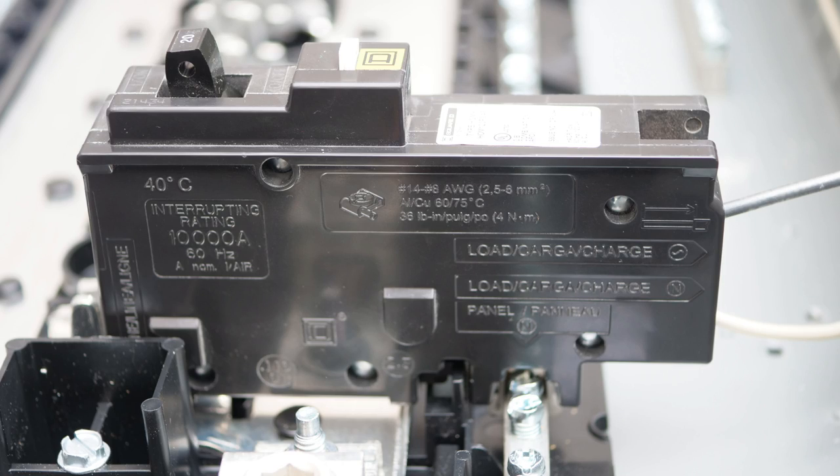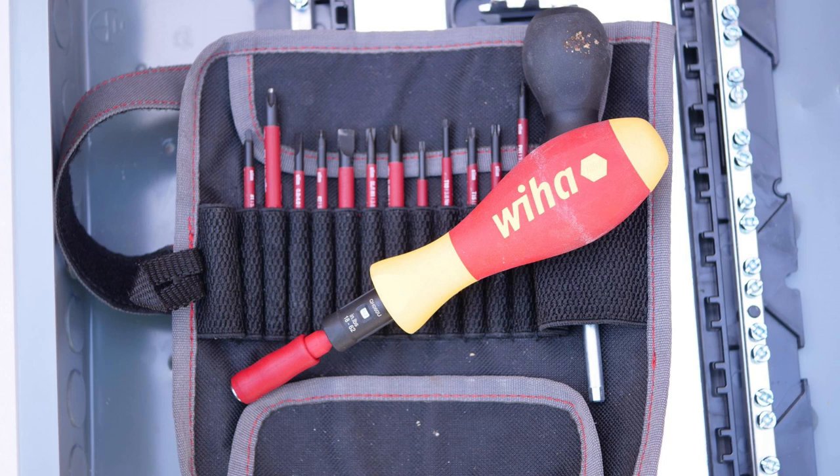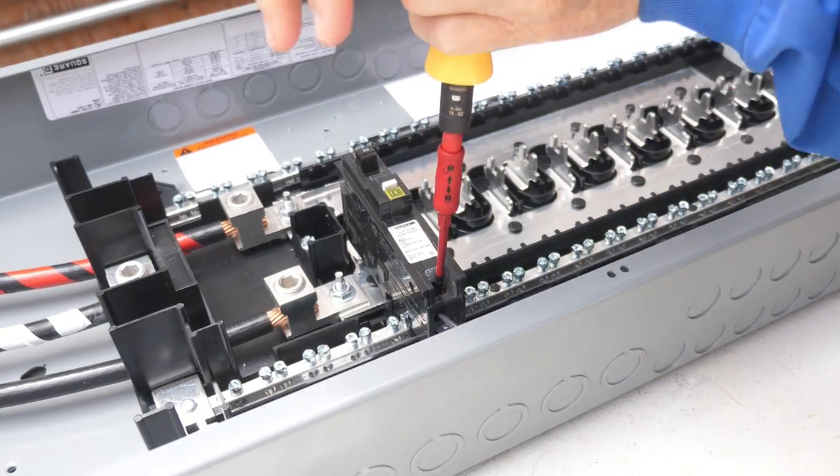Now I'll torque a plug-on neutral style combination arc fault interrupter circuit breaker. The torque value will be found written right on the circuit breaker — in this case it is 36 pound-inches. For this task I'll use my Wiha torque screwdriver and I will set it to 36 inch-pounds. First I'll torque the neutral wire, then I'll torque the black wire to the bronze colored terminal.